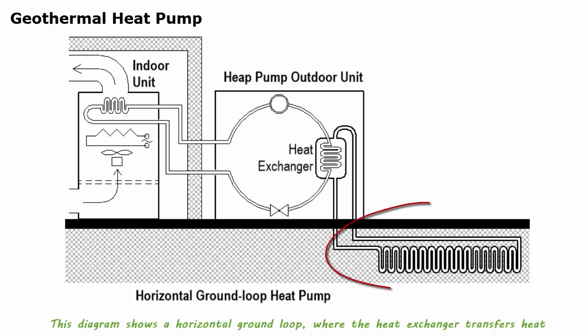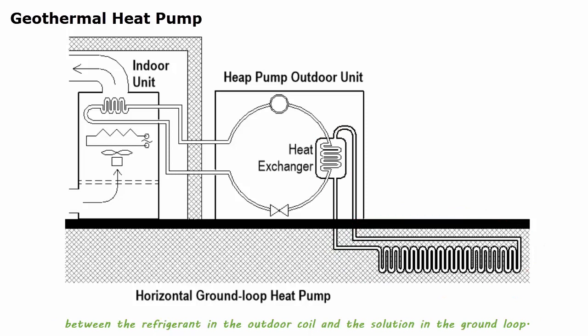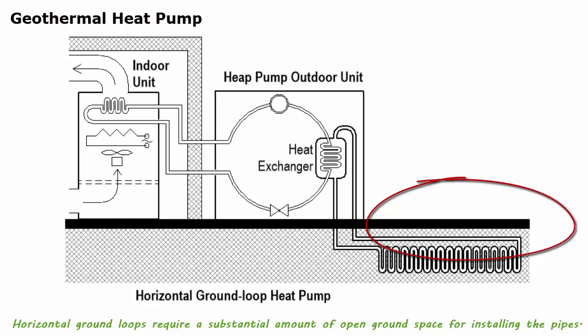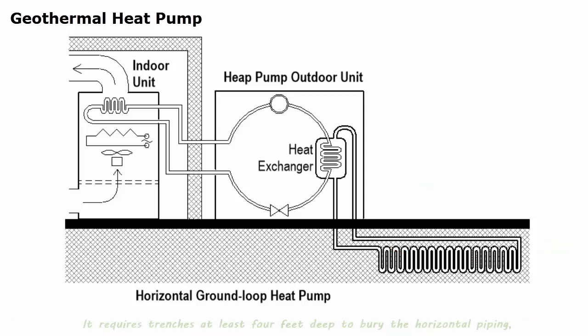This diagram shows a horizontal ground loop, where the heat exchanger transfers heat between the refrigerant in the outdoor coil and the solution in the ground loop. Horizontal ground loop is the most cost-effective configuration, especially for building sites where sufficient land is available. Horizontal loops require a substantial amount of open ground space for installing the pipes. It requires trenches at least 4 feet deep to bury the horizontal piping, which is often coiled and stacked to provide more area for heat transfer.